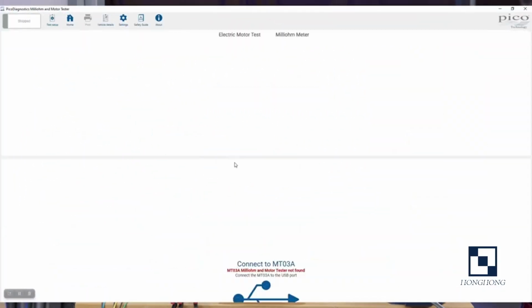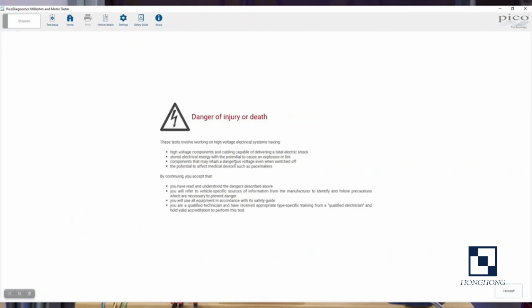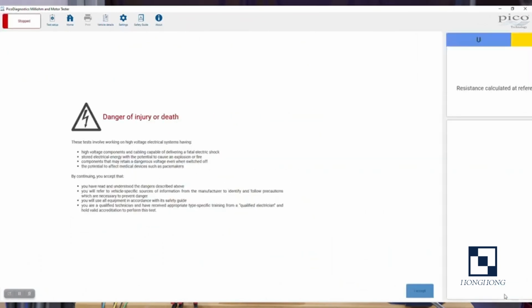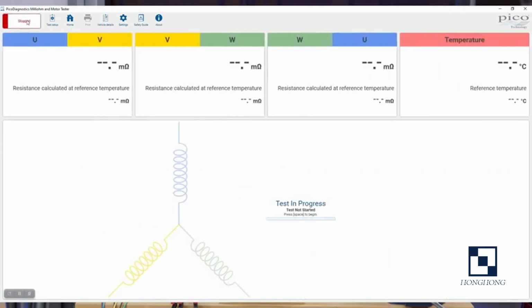Turning to the software, we click on electric motor, confirm connectivity, and accept the warning there. Here we have the UI for milliohm measurement, and we click the start button. You'll notice we have a connection test first of all. We'll read the temperature and then note how current flows through the phases.